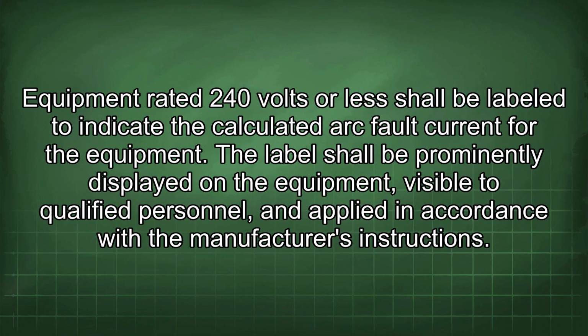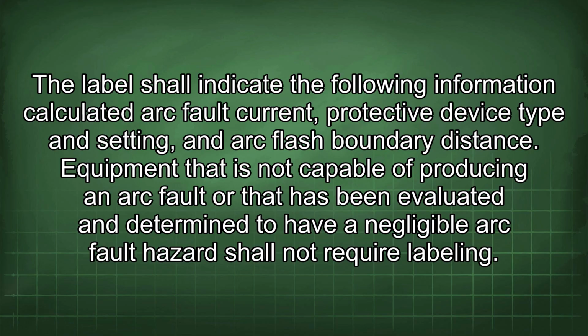Equipment rated 240 volts or less shall be labeled to indicate the calculated arc fault current for the equipment. The label shall be prominently displayed on the equipment, visible to qualified personnel, and applied in accordance with the manufacturer's instructions. The label shall indicate the following information: calculated arc fault current, protective device type and setting, and arc flash boundary distance. Equipment that is not capable of producing an arc fault or that has been evaluated and determined to have a negligible arc fault hazard shall not require labeling.